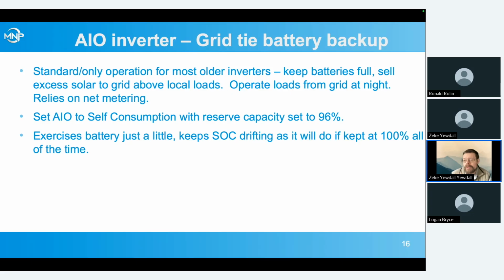We're working on some firmware for our batteries which will actually recalibrate at states of charge other than 100% and correct for this, but for now, this is kind of an endemic issue of just about all lithium batteries out there, that the BMS can drift off from reality when you have very low currents. When you have this grid tie battery backup system, that's precisely the situation you're in, where you've got really low currents just from keeping the inverter itself on at night, and you slowly drift off.